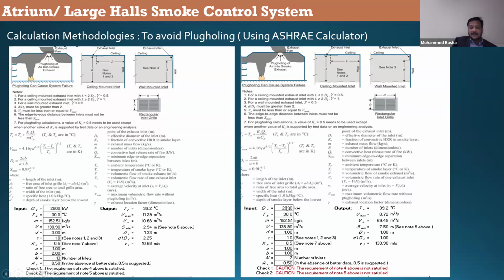Now, look at this here. The same I am using here. Now, a designer is using the wrong values: D as 1, A as 1 and B as 1, and putting 2 exhausts. Will it work? We may see in a normal way, yeah, it has to work, but it will not work. It shows the requirement of note above, 4 is not satisfied, 5 above is not satisfied. What is 4? D by DI must be greater than 2. Why is it not matching? Because for D, you are mentioning only 1 meter of height, which will not work. It needs at least 2 to 3 meters of smoke layer height for large atriums.